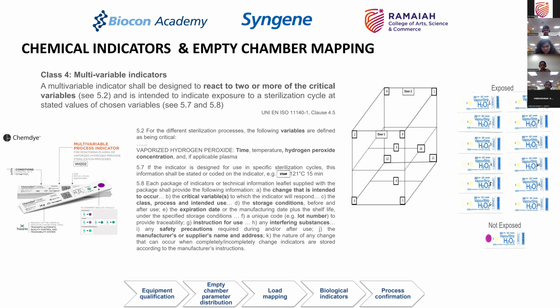Now here you use chemical indicators because, if there is an exposure, that particular purple dot that you see will turn yellow if it has been exposed to the right quantum of H2O2.